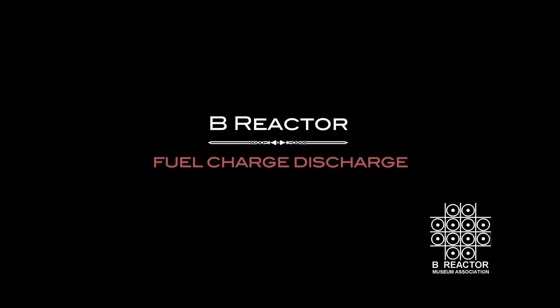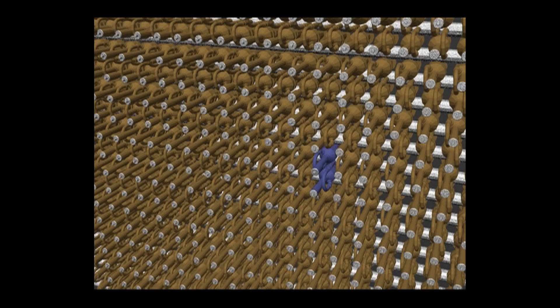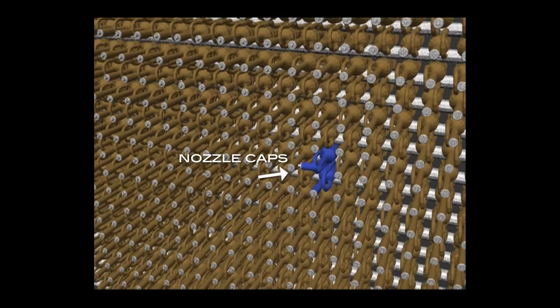Fuel charge discharge. To load a fuel column, the reactor is shut down, the water in the tube row of the tubes to be charged is reduced to a trickle flow, and nozzle caps on both ends of the tubes are removed.